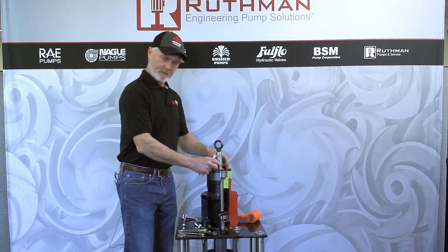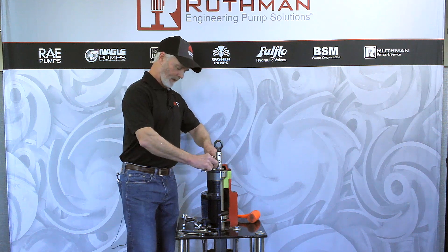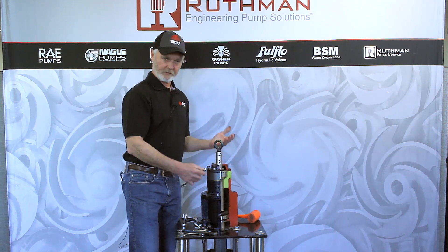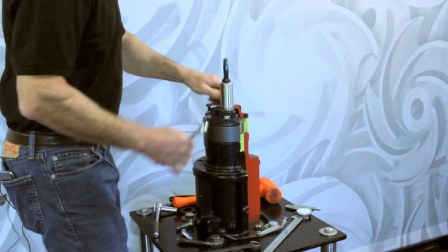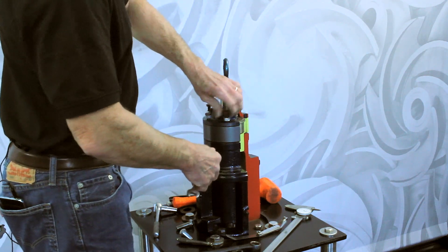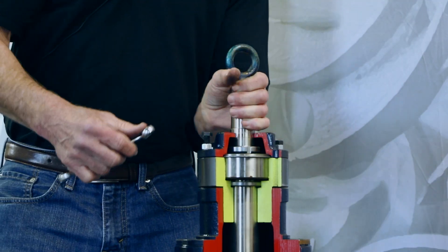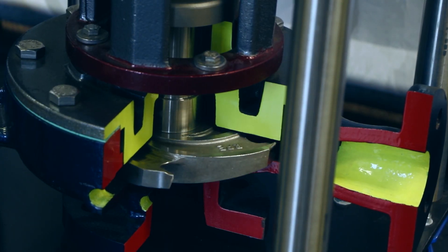Once you've done that, you want to go to the longer bolts. Those will pull the shaft up. To do this, we want to start out with one bolt. Just tighten it until your shaft turns freely. You feel no rub on your housing.